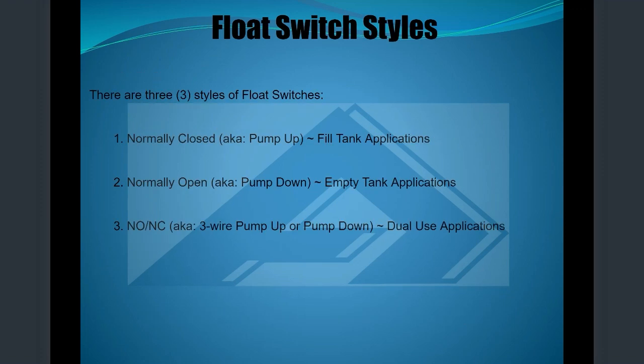Okay, then next. So we have a normally closed. So normally closed means as the float is hanging by gravity, it's down. The internal mechanism in there, whether it's the metal contacts or the micro switch, if it's normally closed while it's hanging, that means there's power able to flow through there. The circuit is closed. So right now that's closed. If it's an alarm control switch, your alarm would be going off, so that would be used as a low-level alarm. If it is used on a control panel, that could be your redundant off float switch. Or on a well system, as your holding tank drops down, it then closes that circuit and then tells your pump to fill that tank back up again.